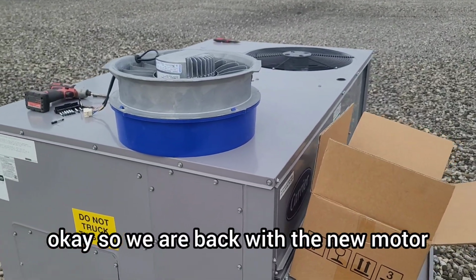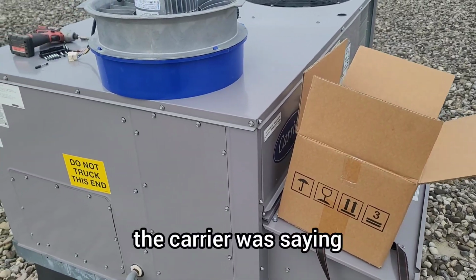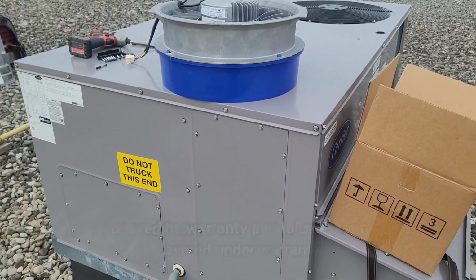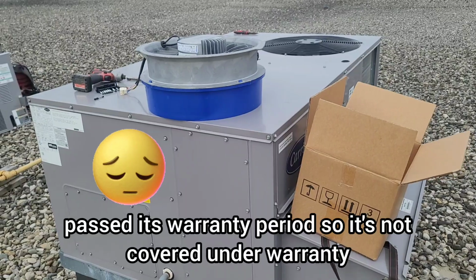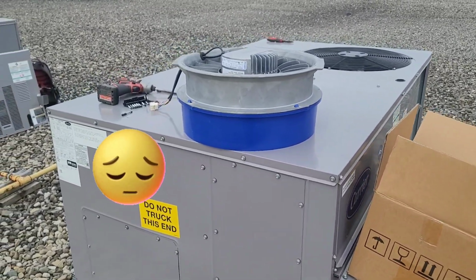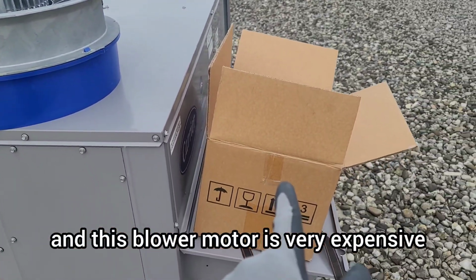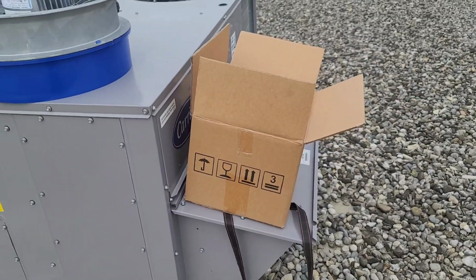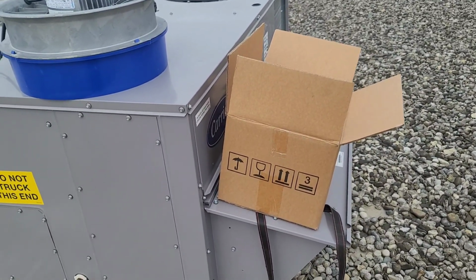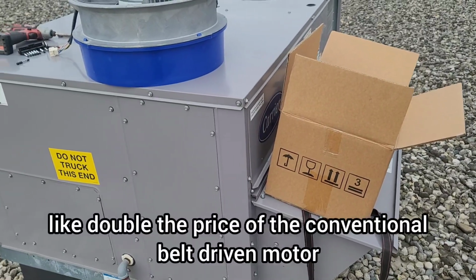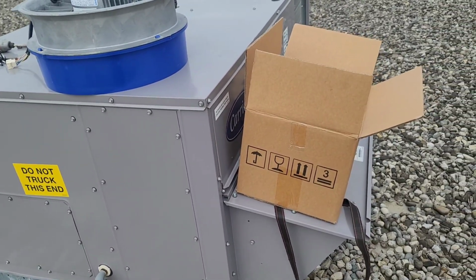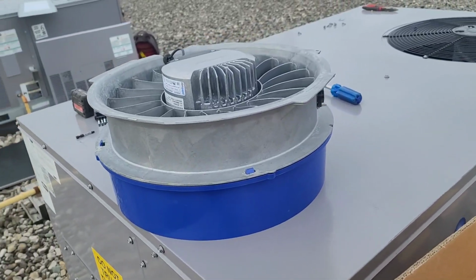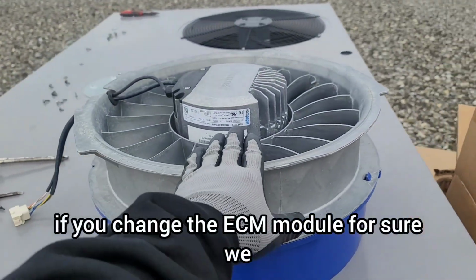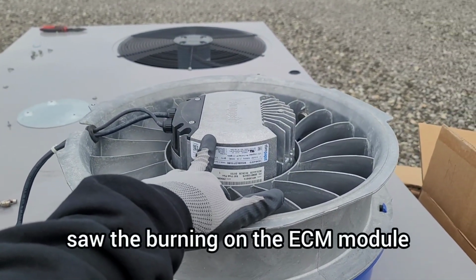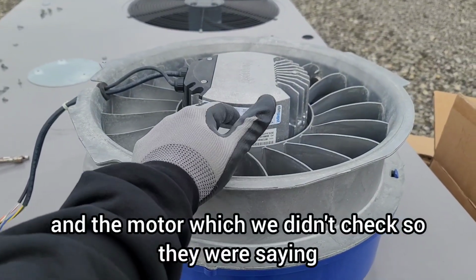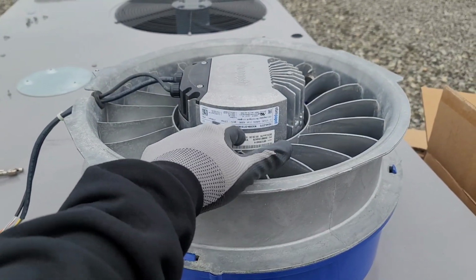Okay, so we are back with the new motor. The carrier was saying that the unit just passed its warranty period, so it's not covered under warranty. And this blower motor is way expensive, it's like double the price of the conventional belt driven motor. They are saying it would be better if you change the ECM module too. For sure we saw the burning on the ECM module and the motor, which we didn't check, so they were saying to change the whole thing.